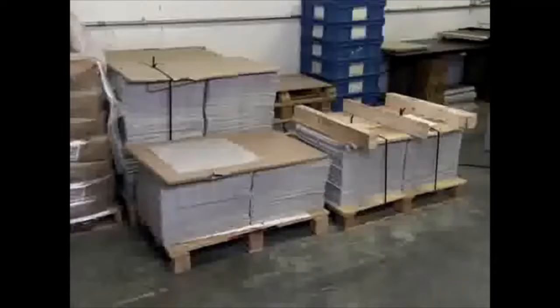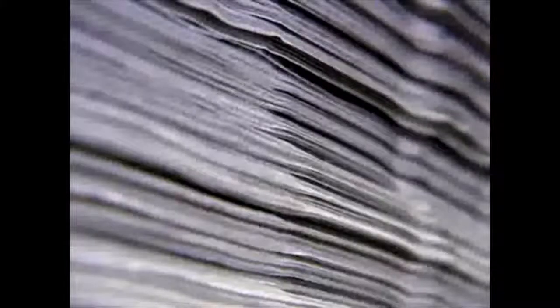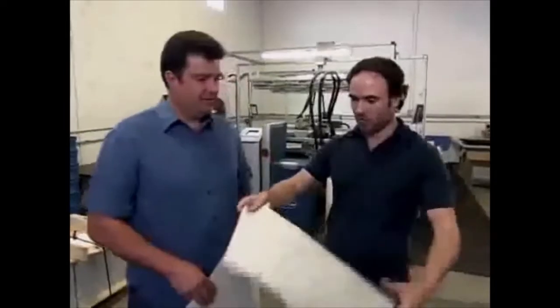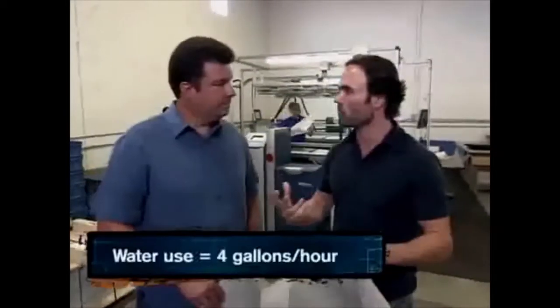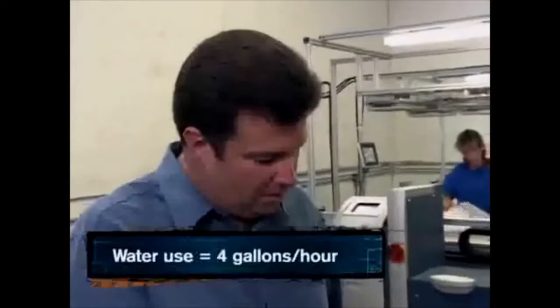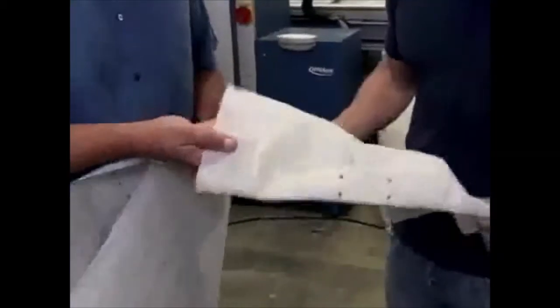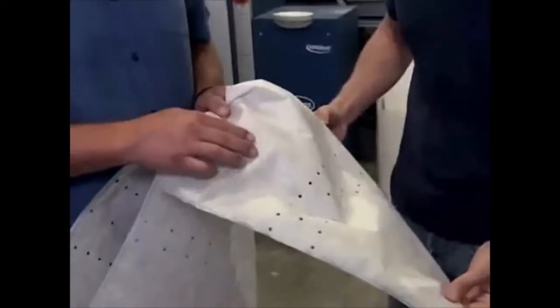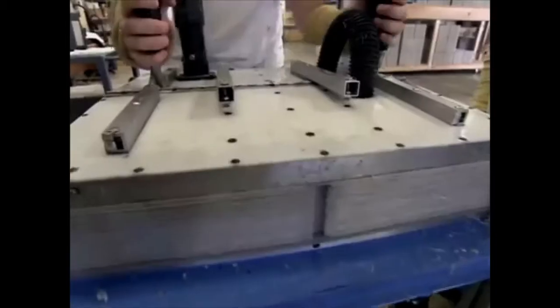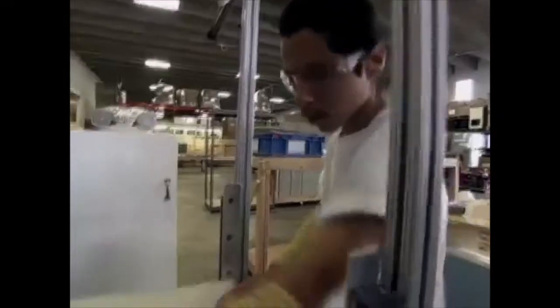How does the Coolerado system do it? Check it out. The heart of the system is the heat mass exchanger, or HMX, made up of thin plastic sheets they call plates. This is kind of the insides of that heat transfer unit. And this plate is a solid piece of plastic on one side. That's the heat transfer surface. It's polypropylene. On the other side is a polypropylene fiber, and that wicks the water. The specially made plates contain channels that draw the moisture.